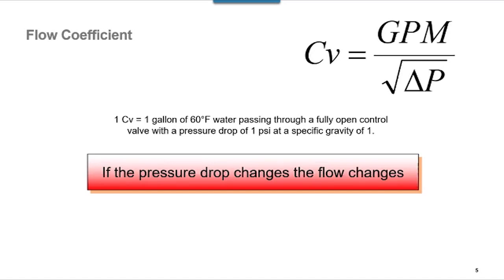This is how we size all pressure-dependent control valves today with flow coefficient, CV. When you look at this formula, two things should come to your mind. If I have a valve with a fixed CV, as the differential pressure rises across that valve, flow is going to go up. And as the differential pressure drops across that valve, the flow is going to go down.